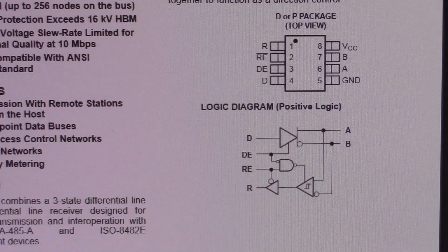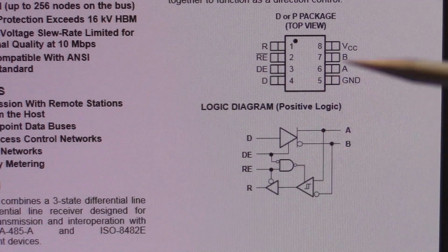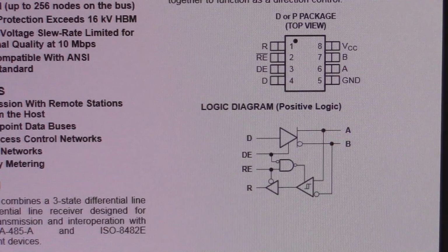I've had a quick look through my collection and I can't find any RS422 transceivers, but I've got lots of RS485 transceivers. The difference between the two interfaces is that rather than two pairs of wires, one for transmit and one for receive as on the RS422 interface, which is more suited to a point-to-point transmission system, the RS485 bus has a single pair of wires which deal with both the transmit and receive of the data.